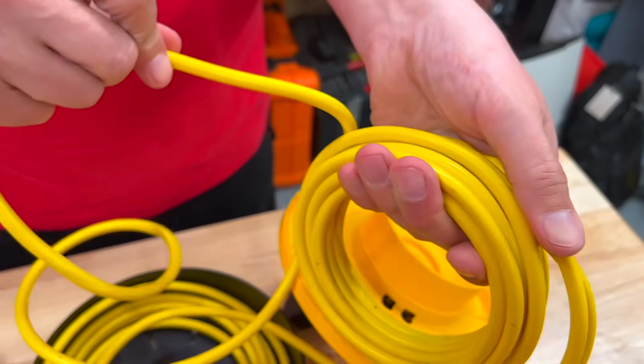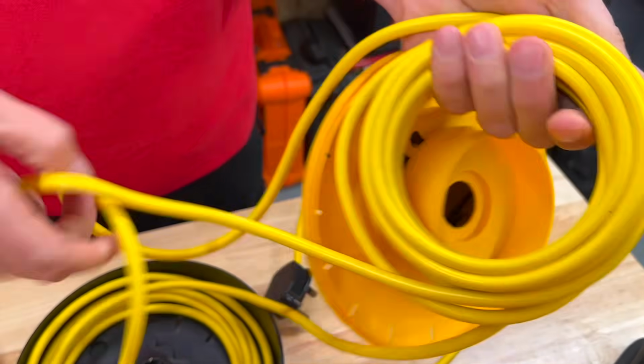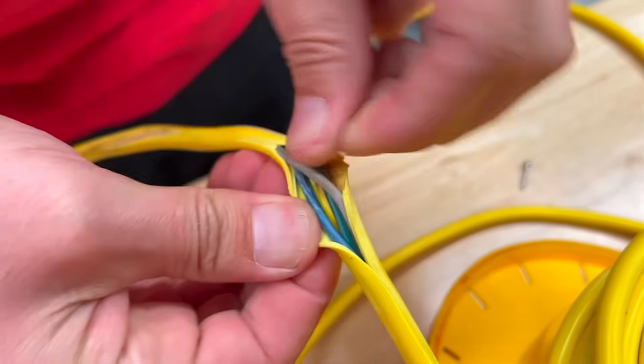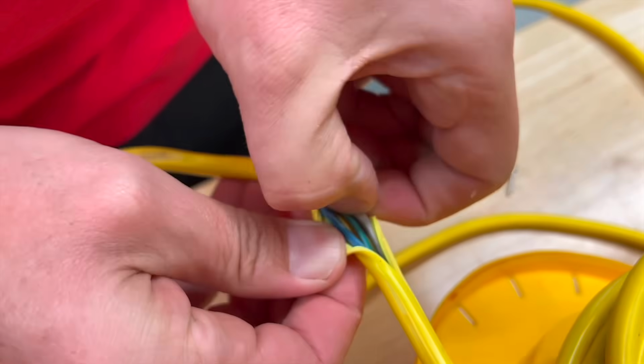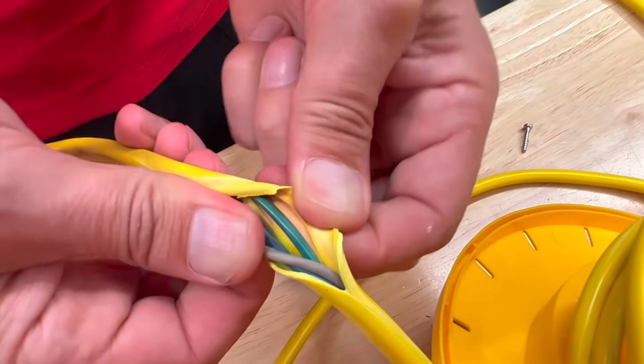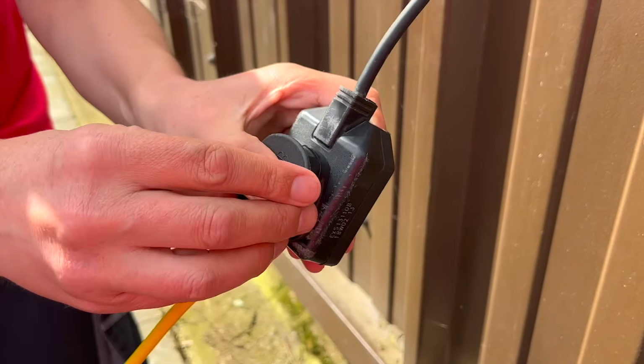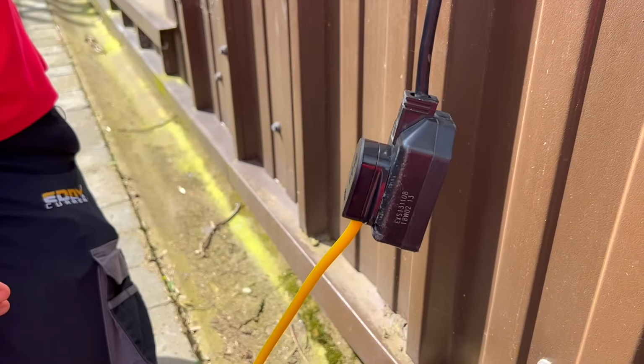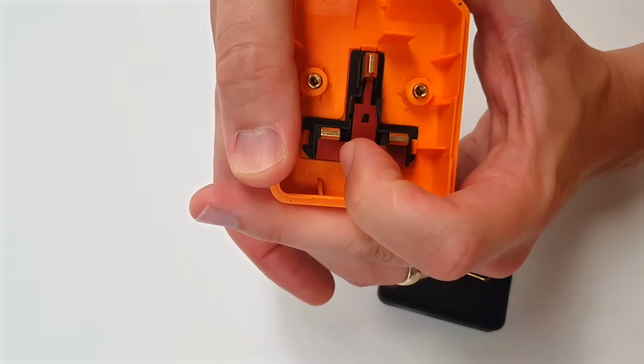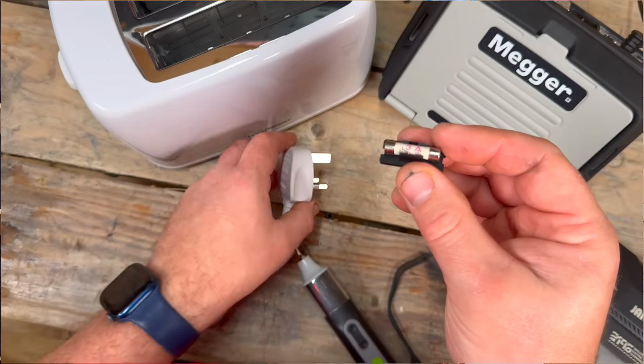The entire length of the flex must be checked, not just the first bit near the plug. Damage turns up where the cable's been pinched, run over, or trapped. If the plug or socket is rewirable, it must be opened so you can verify tight terminations, a working cord grip and functional shutters. If the lead is fused, confirm the cable size and make sure the fuse suits it. A mismatch here is a fire risk.